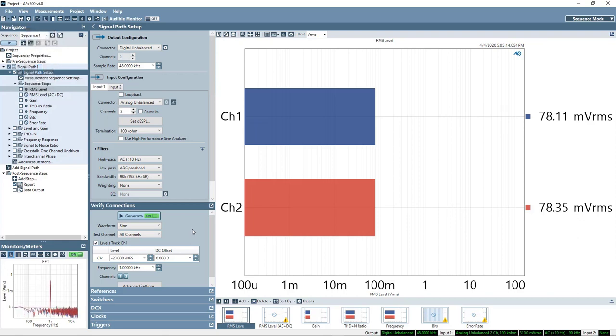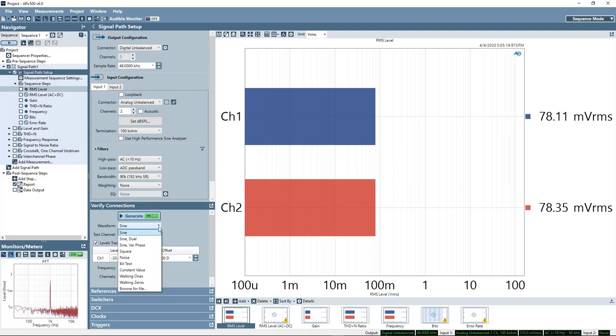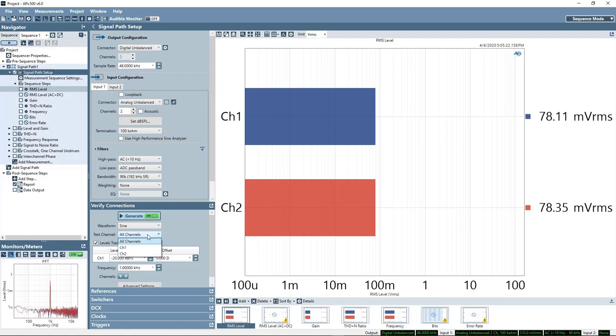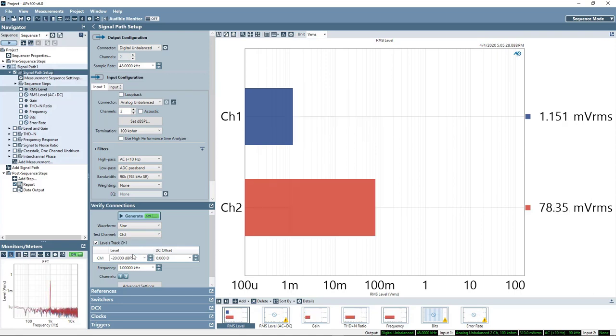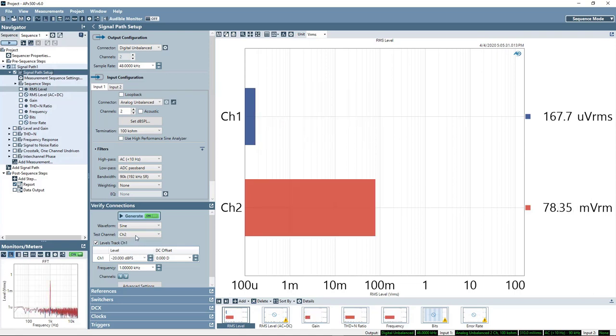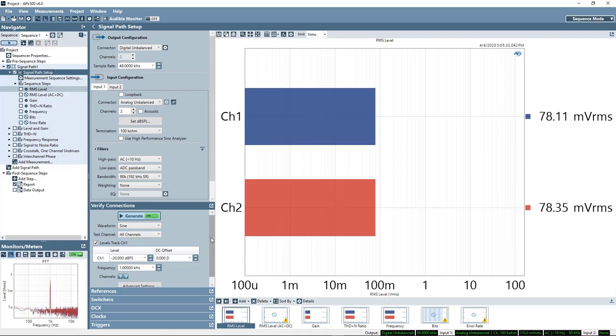So I'll just turn the digital output on and make sure I'm getting a signal back from the device under test. I can go ahead and make sure I've connected those channels. I'll just test one channel at a time and make sure I get signal back on the appropriate channel.